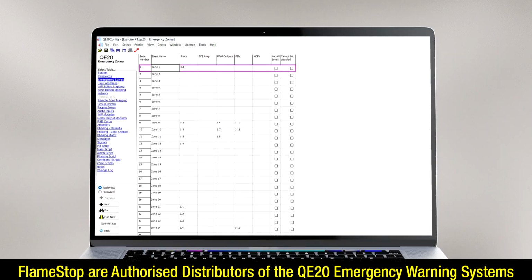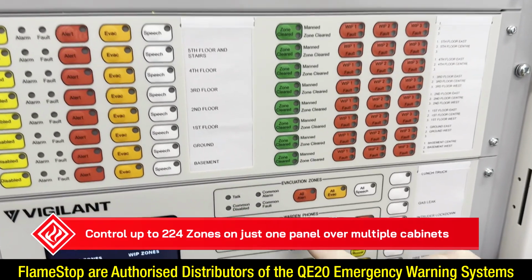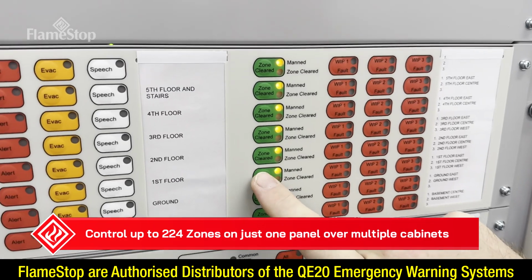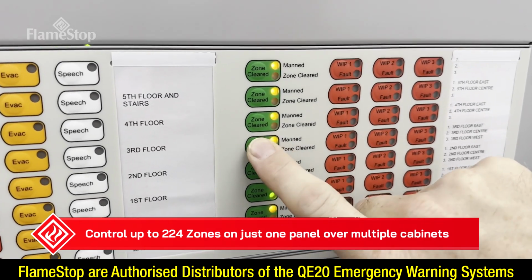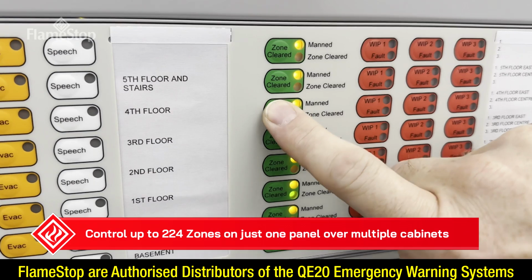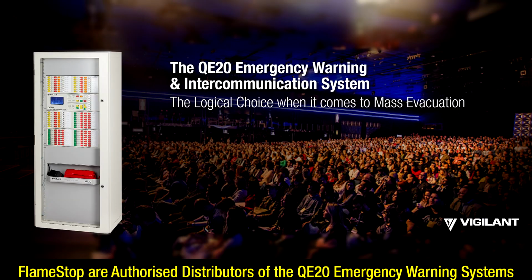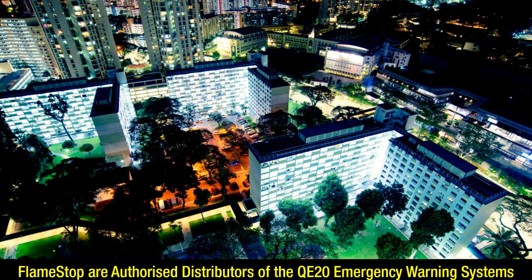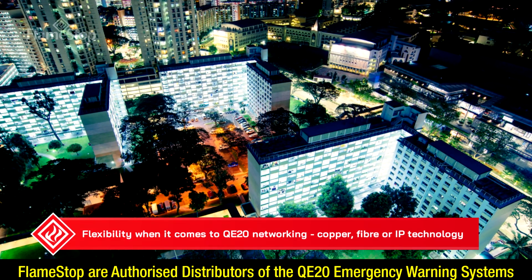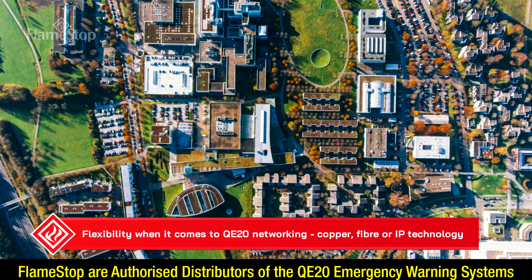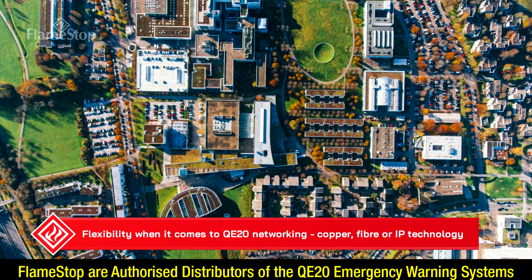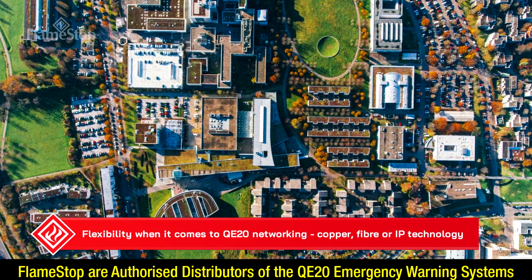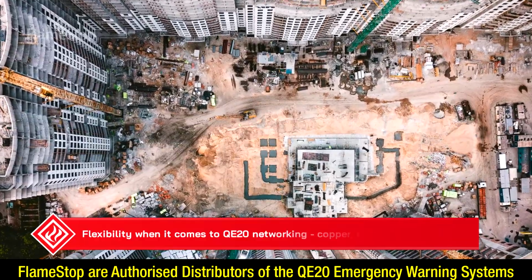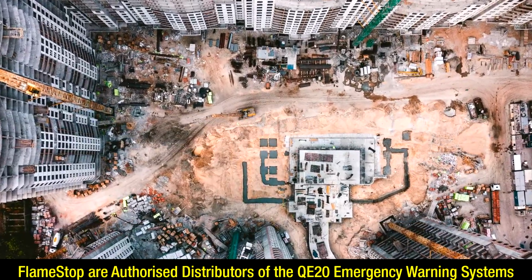Up to 600 zones can be programmed internally on a QE20. You've got the ability to control up to 224 evacuation zones on just one panel and over multiple cabinets. The QE20 is the logical choice when it comes to mass evacuation. The system is expandable to a 64-node network, making it ideal for any of the largest sites throughout Australia. Networking can be over copper, fibre or using IP technology for voice and data.